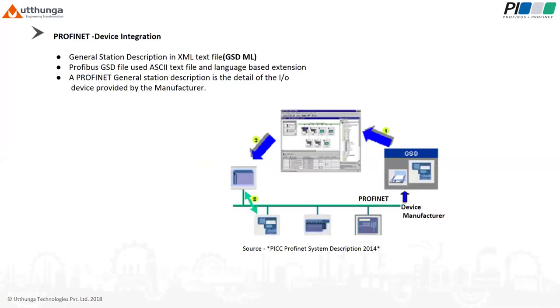Coming to device integration, General Station Description. In PROFINET, this is GSD-ML. It's called GSD-ML since the file is described in XML format. The content of the GSD file contains configuration information, parameters, modules, diagnostics, alarms, and device identification. The XML-based GSD-ML describes the properties and function of the PROFINET IO field devices. The field manufacturers have to provide this GSD-ML. Thus, in the image, we can see if the field manufacturer provides us the GSD-ML, using an engineering tool I can download and upload the device and start communication with the IO devices. Below the PROFINET line, you can see the IO devices. Thus, I can start communication.